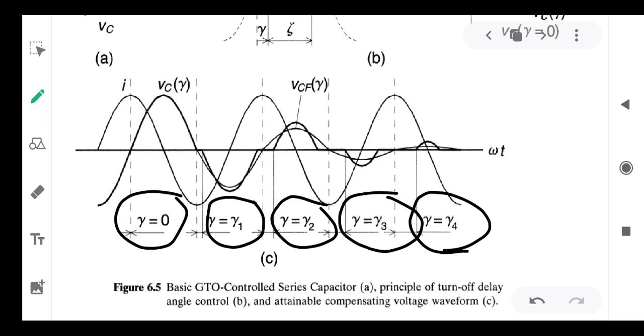But the complete waveform is not sinusoidal. So therefore, there is a chance of injection of voltage harmonics into the system. This is turn-off delay angle control, whereas in TCR, turn-on delay angle control is adopted.